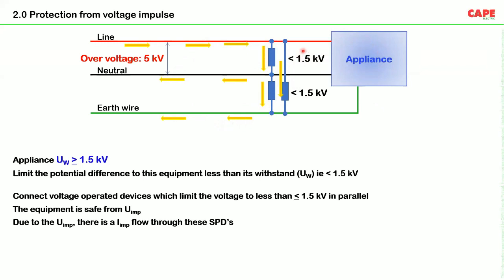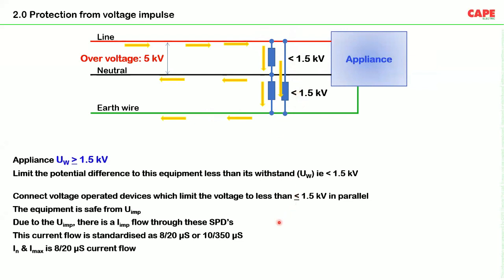Why is the current flowing? Because in order to limit the voltage to less than 1.5 kV, the impedance of this device is reduced to a lower level, because the device is offering a low impedance within a short time. As a result, the current flows through this device, and we create a situation called equipotential bonding. The current flowing through these devices can be either 8 by 20 microseconds or 10 by 350 microseconds. In the last seminar, we discussed the difference between 8 by 20 and 10 by 350 microseconds. Of course, a short 2 to 3 minute video has been uploaded to our blog. You can have a look and find out what exactly 8 by 20 and 10 by 350 microseconds mean. So basically, this is how your appliance is protected. So you have an appliance. Most important, we should find out how much voltage this appliance is able to withstand.